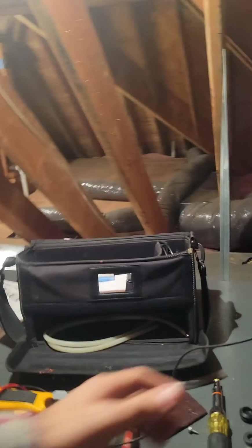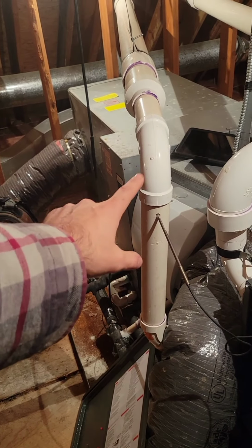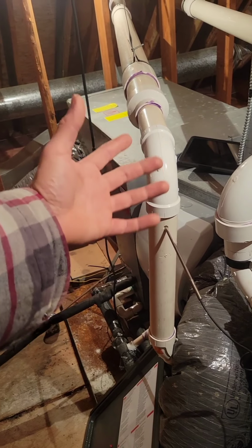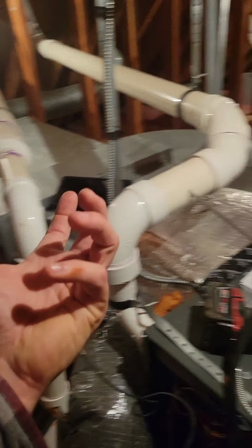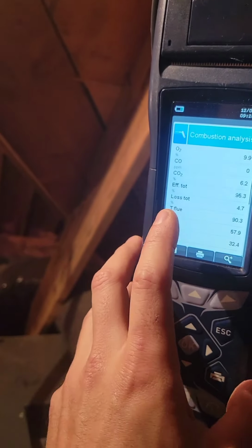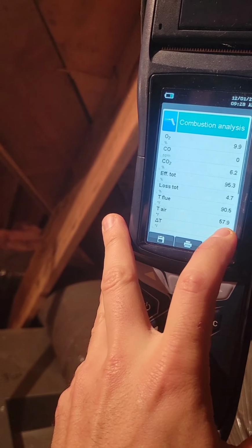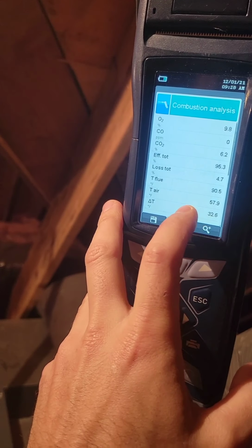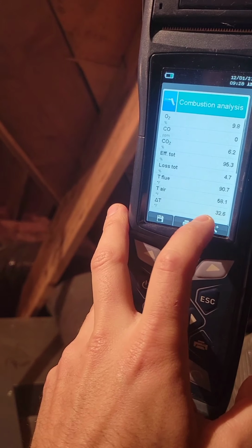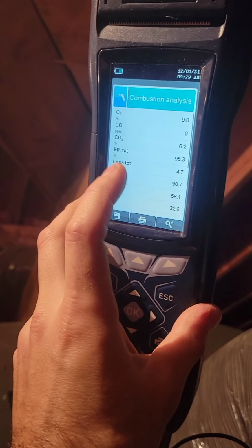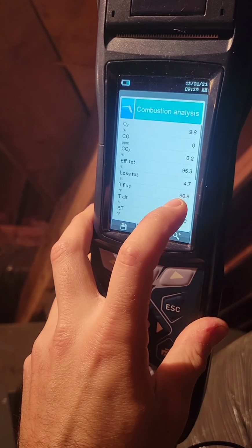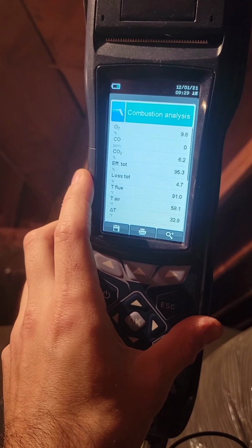Also, just a quick note, opposite to this one, this takes the intake from the outside. So you can see I've attached a K-type thermocouple to my outdoor intake piping. So now we're actually measuring the air from the outside, which is 57 degrees. Delta T is around 32 degrees, temperature on my stack is about 90 degrees.